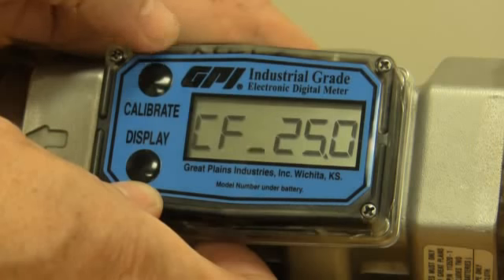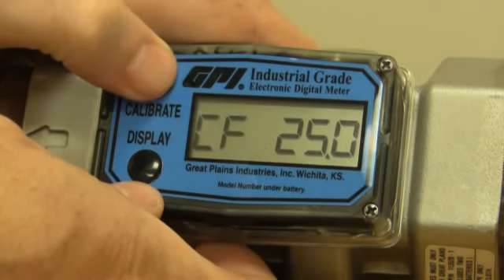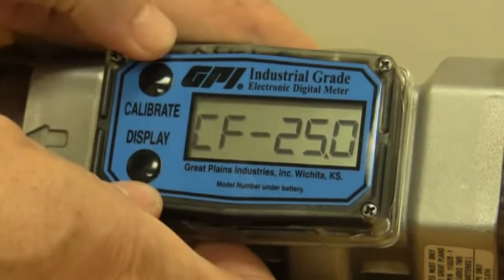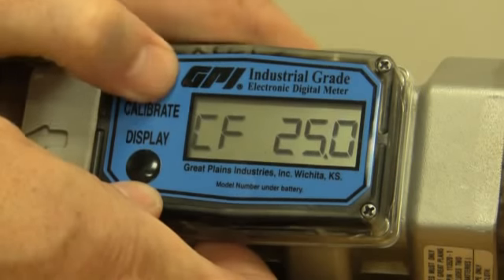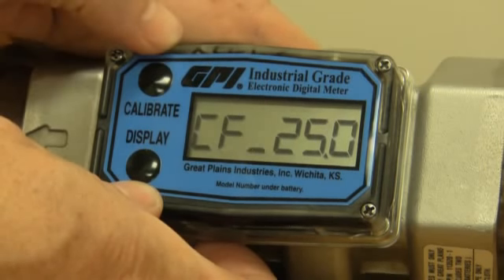Okay, now I did mislead you a little bit there. This line right here wasn't where you can put a digit. That is where you're going to have a positive or a negative. With it being down low, that's a positive. Push the calibrate button once, you can go back to the middle here, that's a negative. So do we want it to be negative 25% or positive 25%? The rule of thumb for that is if your reading is higher than what the container was, then you want a negative. In our case, the reading was lower than what the container was, so we want a positive.